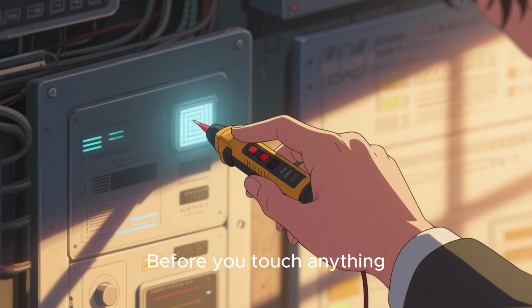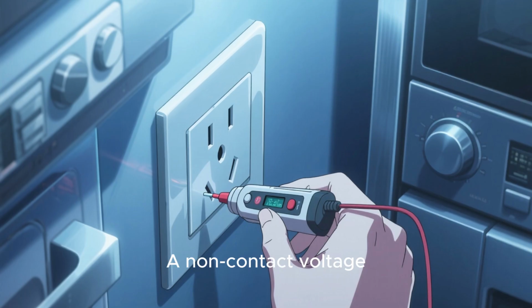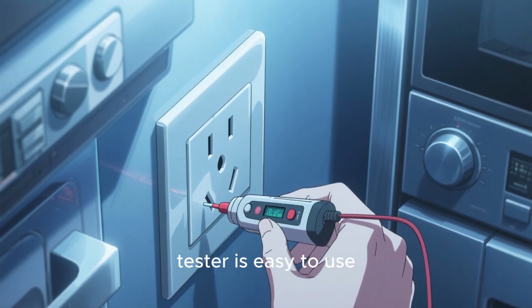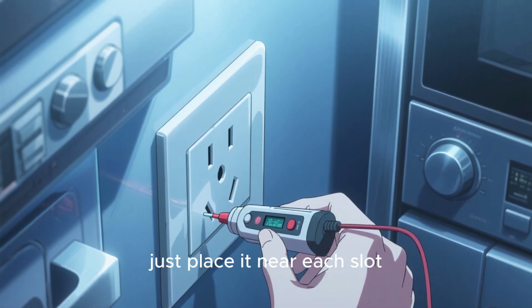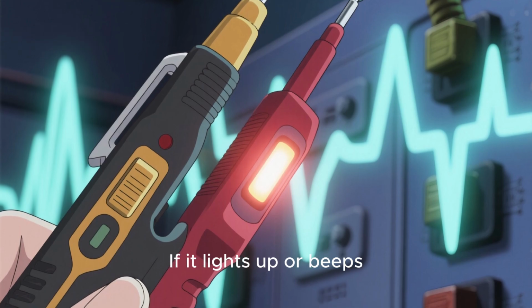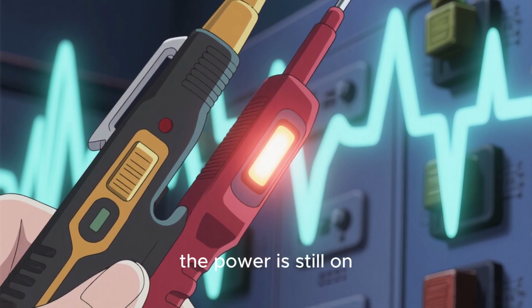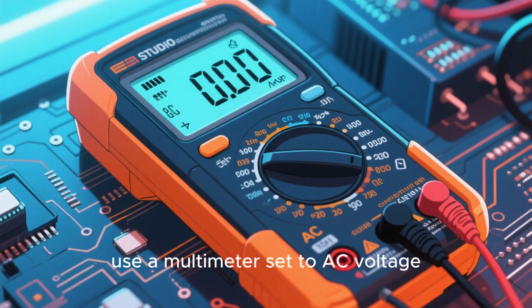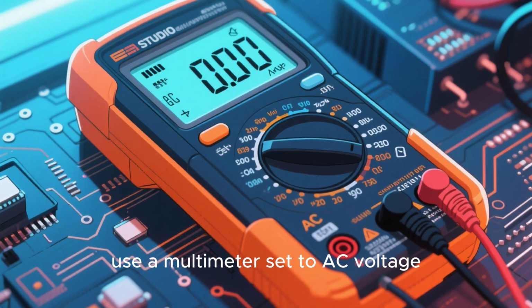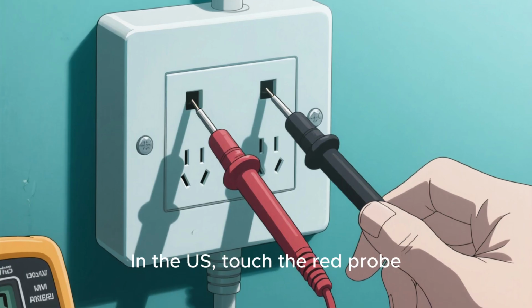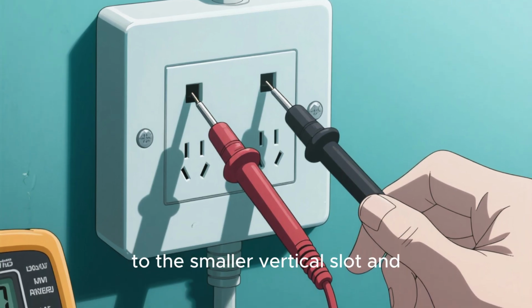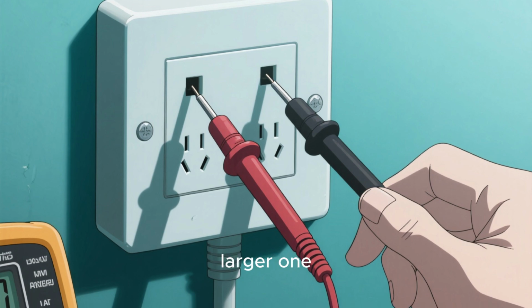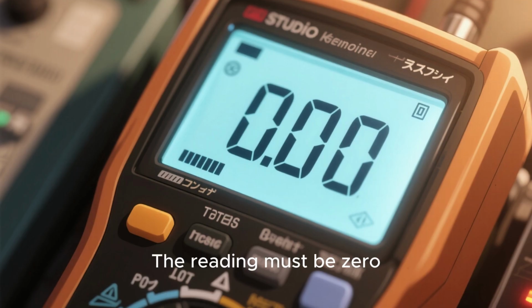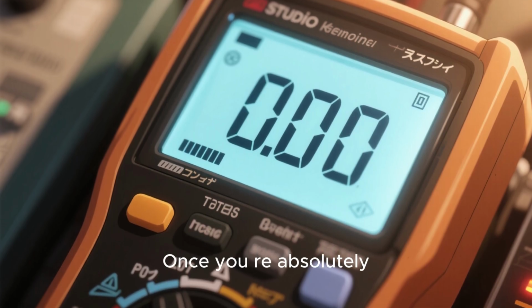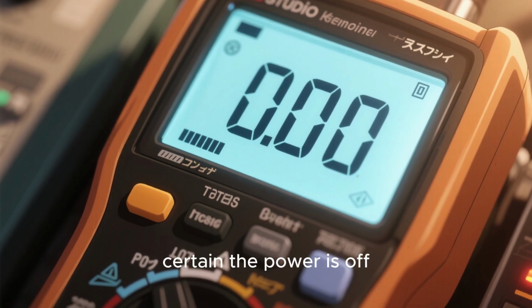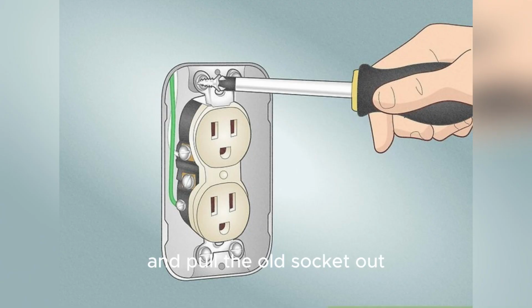Before you touch anything, you must test for voltage. A non-contact voltage tester is easy to use. Just place it near each slot. If it lights up or beeps, the power is still on. For a more reliable check, use a multimeter set to AC voltage. In the US, touch the red probe to the smaller vertical slot and the black probe to the larger one, then the round ground hole. The reading must be 0. Once you're absolutely certain the power is off, you can unscrew the faceplate and pull the old socket out.